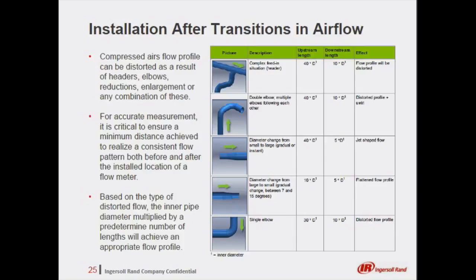As compressed air flows through a piping system, headers, elbows, and reductions and enlargements can all have an effect on the flow profile. A minimum distance both before and after these pipe transitions should be observed to ensure accurate measurements. Recommended upstream and downstream lengths of pipe are made based on these various pipe transitions, calculated by the number of lengths of inner pipe diameter.